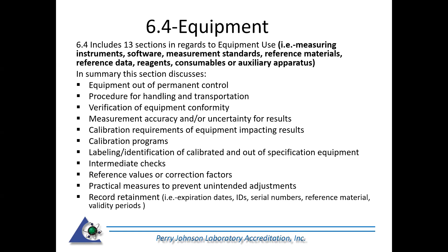So let's look at a few examples under 6.4, equipment. In this particular situation, the laboratory was not able to show that a laboratory balance was calibrated prior to use. The objective evidence that we saw was that the OHAUS analytical balance used by an analyst on 6/29/19 was not calibrated prior to use. That's what led us to the finding, and this was a violation of 6.4.6, where it says measuring equipment shall be calibrated. I don't need to read every bullet point, but that's the area we wrote that up on. So for cannabis and hemp labs or any lab, just make sure that whatever equipment you're using, such as balances in this industry, which does impact the test results, this would be an area where we would find a problem if it was not calibrated.